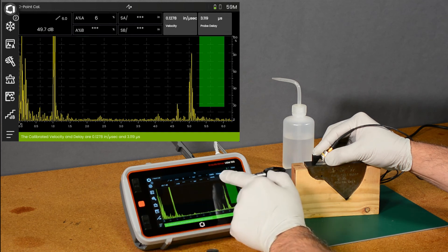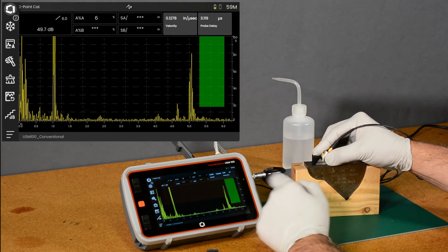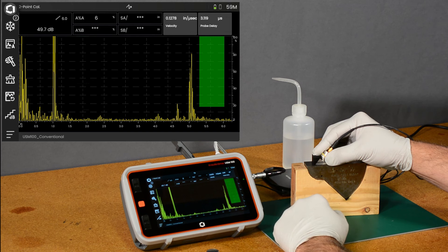And it calculates the velocity at 0.1278 inches per microsecond and our probe delay at 3.119 microseconds.